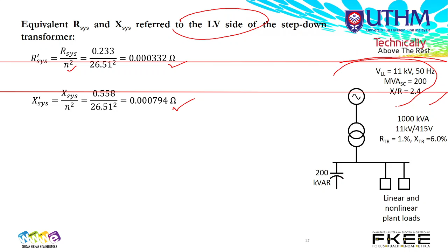the transformer, at LV side, same process. Okay, it's given in per unit form, you need to convert to real value, R per unit times Z transformer base. Z transformer base equals V base square divided by S base.